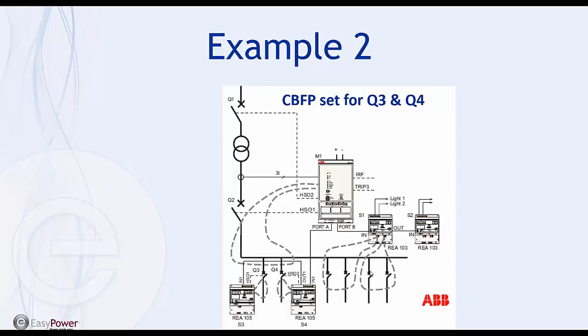There is no selectivity. If you have an arcing fault, then that light information is passed back to the main unit, and if the current exceeds the fault detector level that you set, then you're going to trip the entire bus, no selectivity. If you have an arcing fault on Q3 or Q4, if the current exceeds the fault detector value, and it almost certainly will, that current information is passed to the REA105.